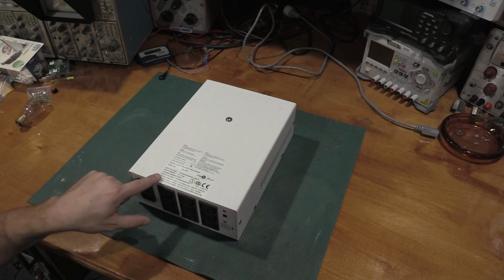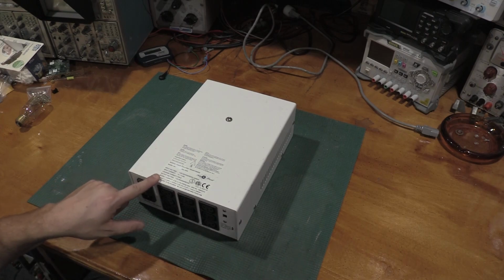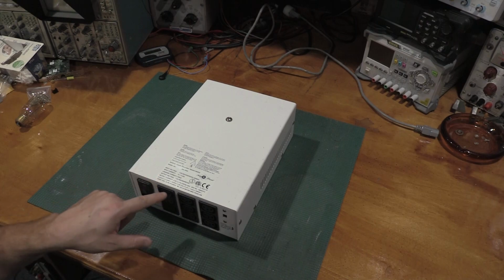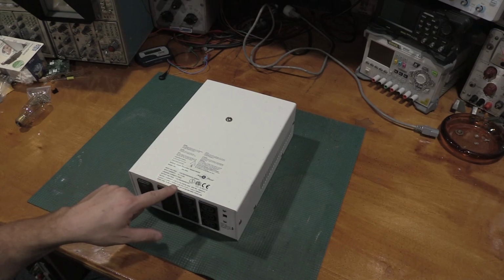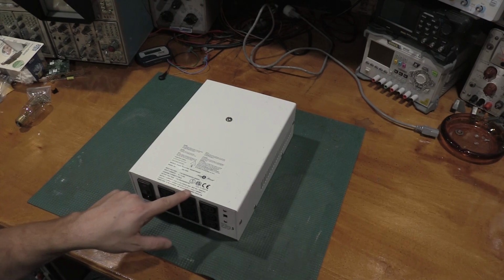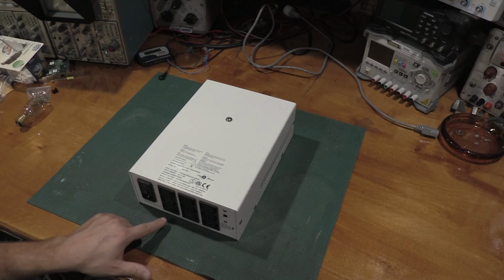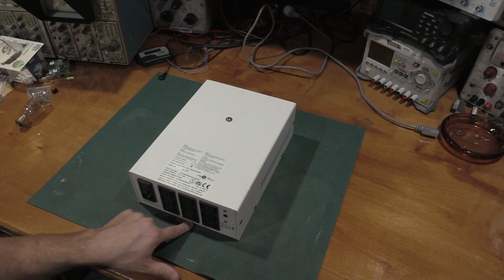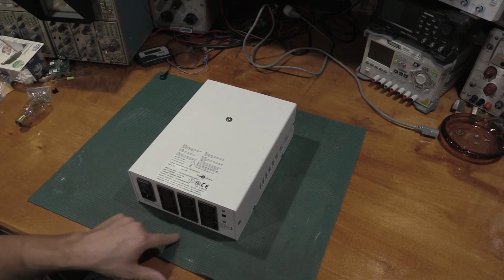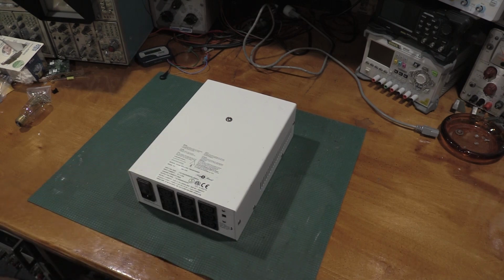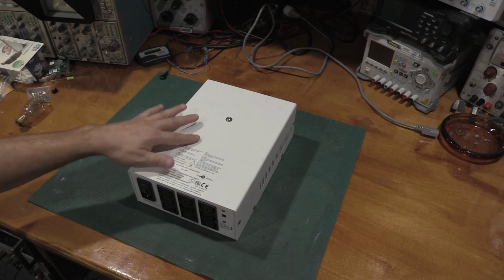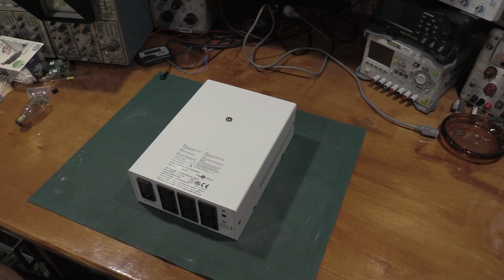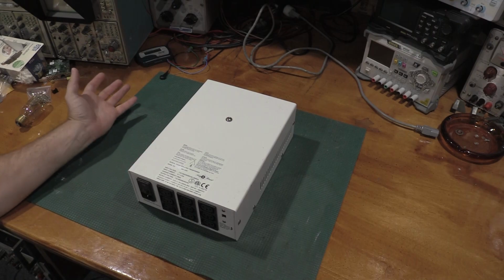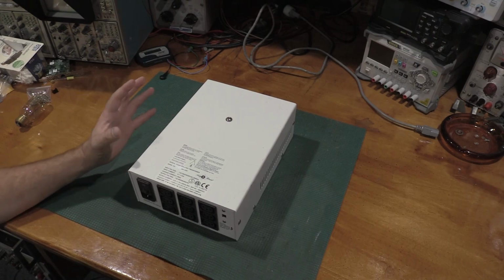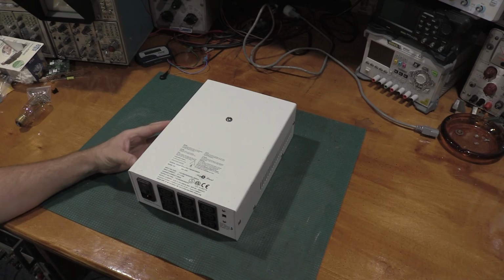So this one specifically says output current 8.34 amps or 4.17 amps, 100 VA max. Down here it says the same thing, except it says 1,000 VA max. So it is a 1,000 VA transformer. I have driven this at 8-ish amps before, so it'll hold up. And I needed the isolation transformer of this amount of current. This is about the smallest package an 8 amp transformer gets in.